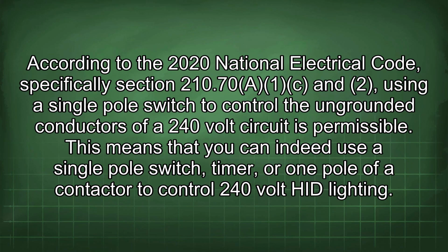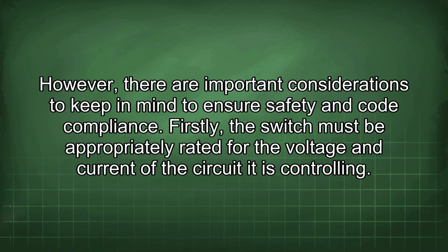According to the 2020 National Electrical Code, specifically Section 210.70(A)(1)(c) and (2), using a single-pole switch to control the ungrounded conductors of a 240-volt circuit is permissible. This means that you can indeed use a single-pole switch, timer, or one pole of a contactor to control 240-volt HID lighting. However, there are important considerations to keep in mind to ensure safety and code compliance.